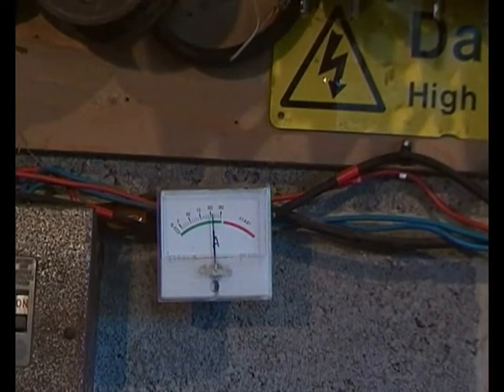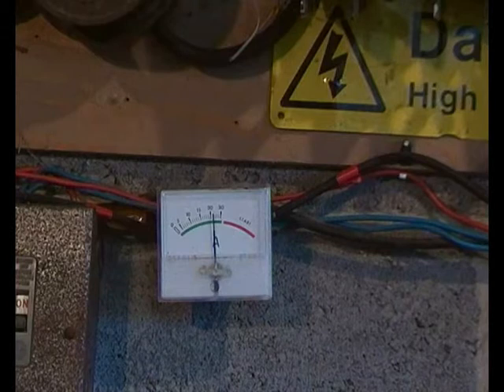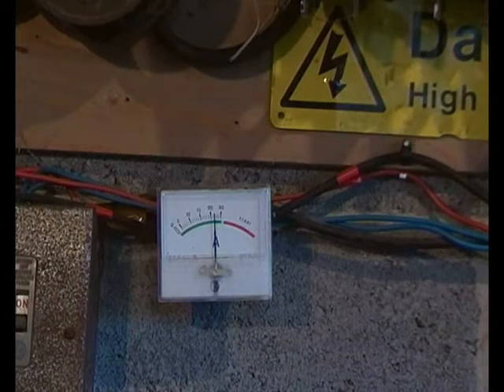Total solar — the sun's coming out from behind a cloud. 20-odd amps, which is a kilowatt — 25 amps. The panels are cool and there's a breeze. So even though the sun's coming through a lot of atmosphere, cold panels provide more voltage. As the panels warm up, the voltage goes down.